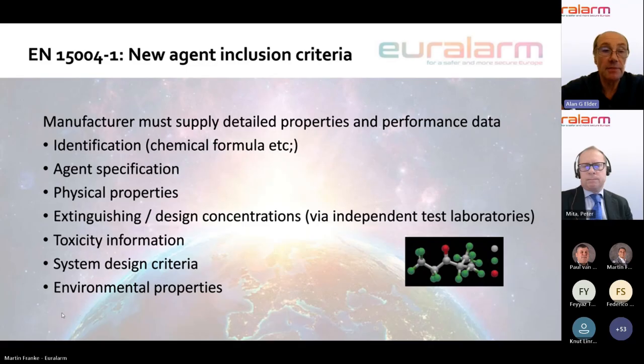So that now is mandatory according to Annex J of the standard, that if a new agent is offered into the technical committee, that the manufacturer, before it would get to the stage of being published, would need to provide all of that information, and for that to be peer reviewed within the technical committee as meeting the requirements. Next one, Martin, please.